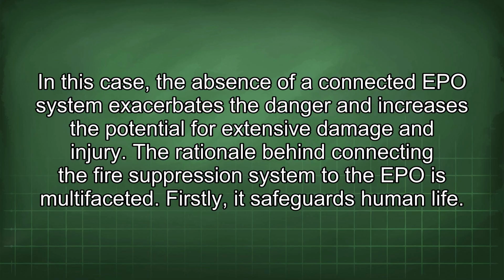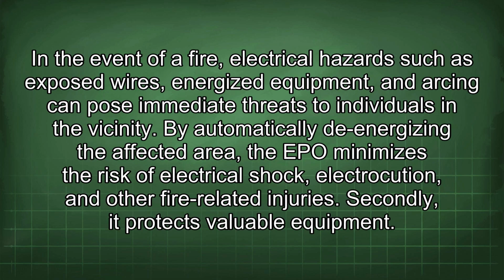The rationale behind connecting the fire suppression system to the EPO is multifaceted. Firstly, it safeguards human life. In the event of a fire, electrical hazards such as exposed wires, energized equipment, and arcing can pose immediate threats to individuals in the vicinity.